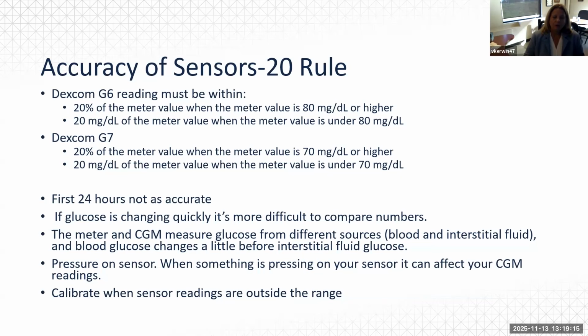And then also, there's pressure on the sensor, which can cause a false hypoglycemic alert. Sometimes if somebody's laying on the sensor that's on their arm, they may get an alert telling them their blood sugar is low. So I usually tell them, if you're not having symptoms, do a finger stick to confirm, because it might just be compression hypoglycemia, meaning that if you roll off the sensor, it will readjust and probably show a number that's not low. So sometimes that will happen. They'll get a false low on there. So that's something they need to be aware of.